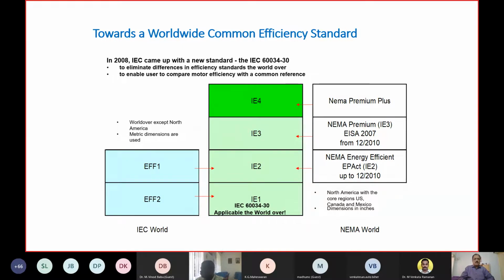But importantly, while IEC testing was being adopted by most of the world, we were assuming stray losses as 0.5% across board for all the outputs. That was disputed in the year 2002, and by the year 2007, a new efficiency testing standard was adopted as IEC 60034-2-1. That was the first time that IEC adopted a new efficiency testing standard, where they talked about accurate measurement of stray losses. And 2-1 in 2014 was a revision where only one method was permitted for efficiency measurement under the IEC.